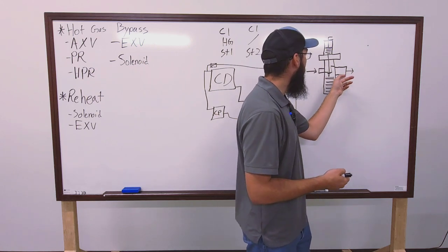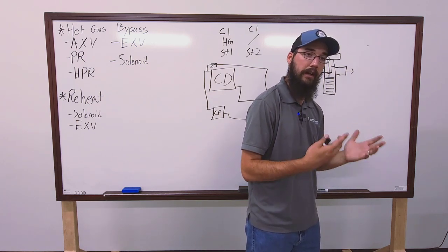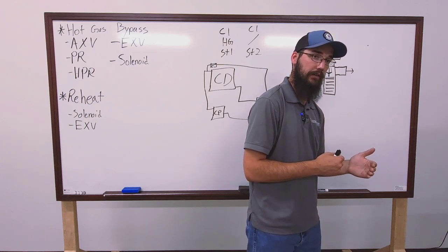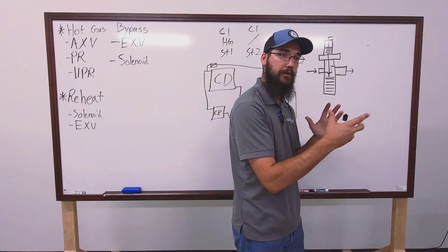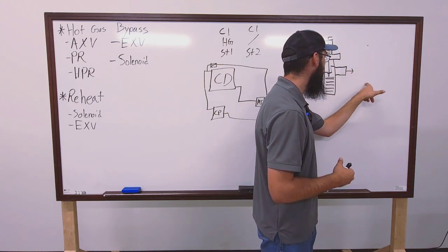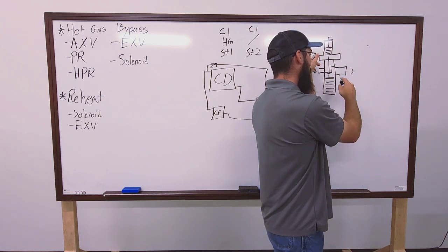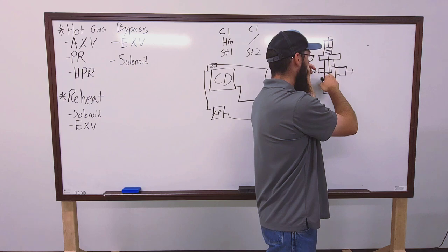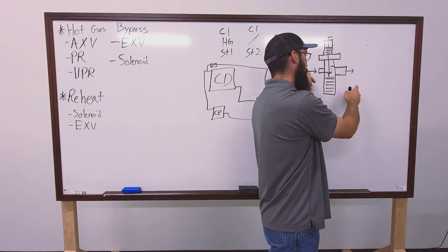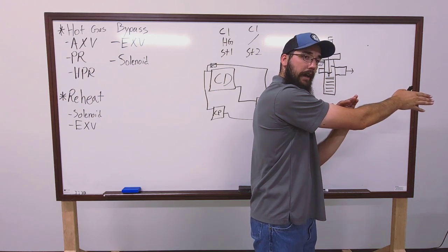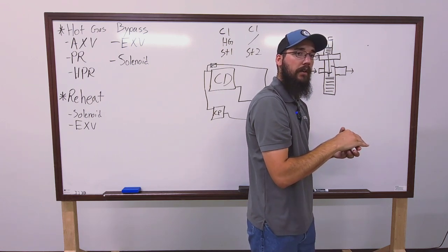And, what will happen is, now this does react to a degree to ambient temperatures. That's one of the things about AXVs, is they're pressure differential devices, but they do, that power head will respond to pressures, or to temperature changes. Anyway, ultimately, though, it's really monitoring that pressure differential. And so, when it sees the differential begin to increase beyond its spring set points, then it will begin to force this valve open, and it will allow more flow through, which will lower the head pressure some, and it will allow more hot gas to enter the suction pressure, which then raises your saturation.